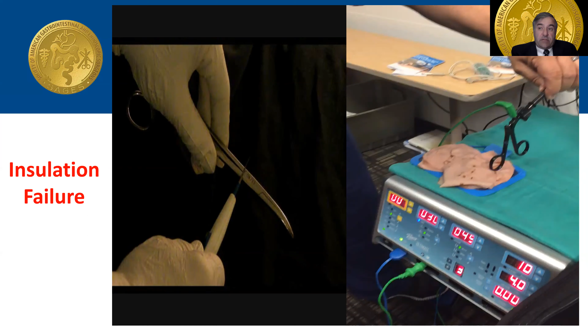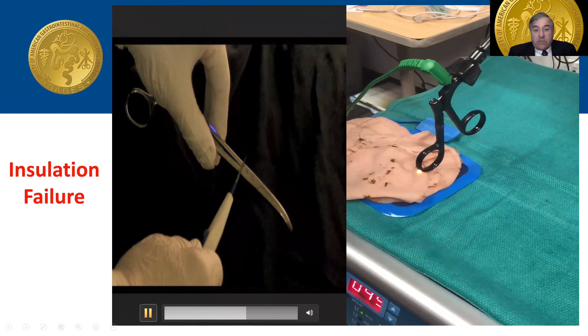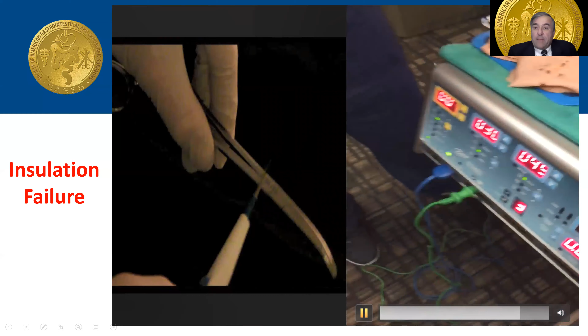All of you have experienced burns because of that. You can see that the energy is transmitted through the instrument and then causes a burn of the instrument holder. This video shows that even new instruments, when unwrapped for the first time, can have insulation failures.